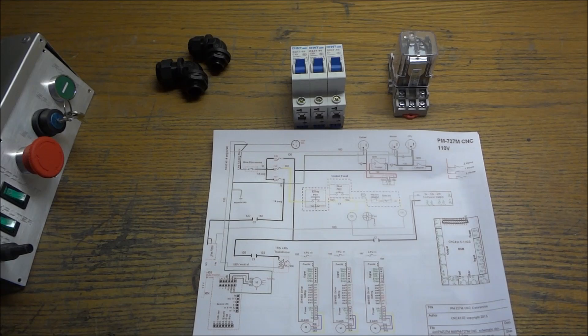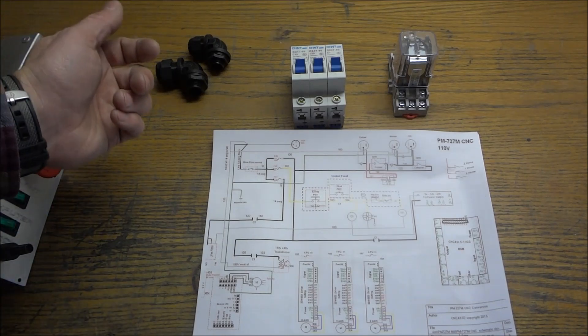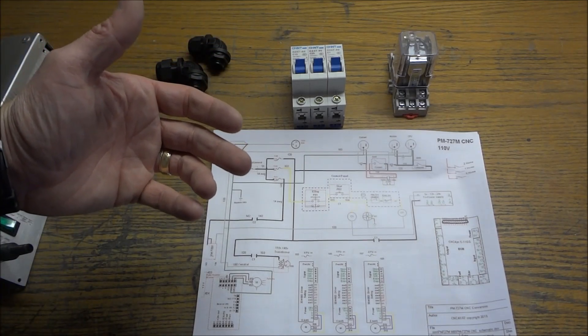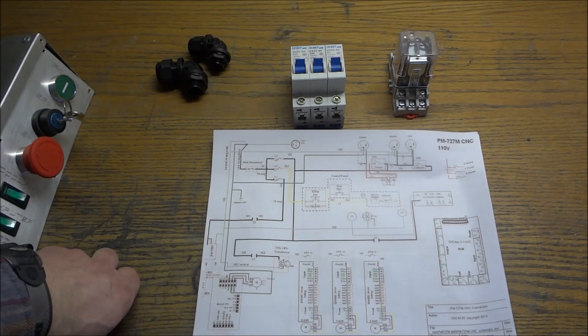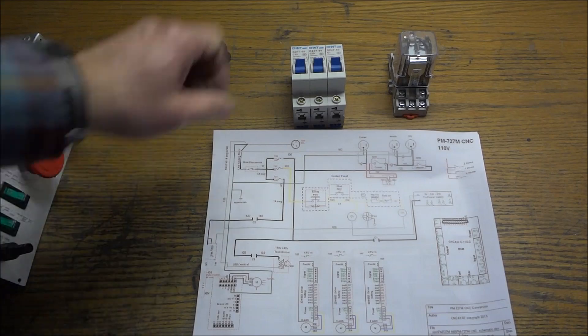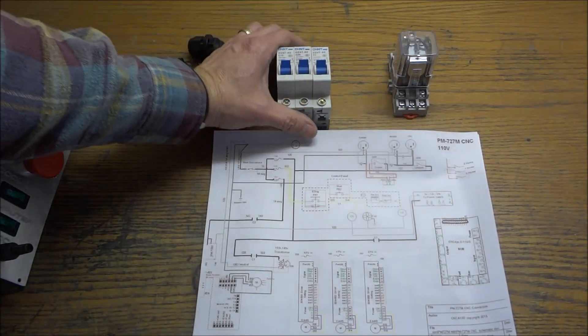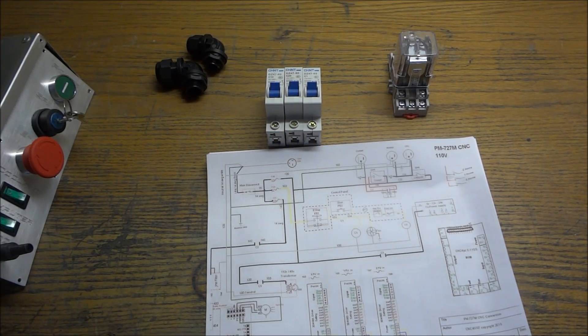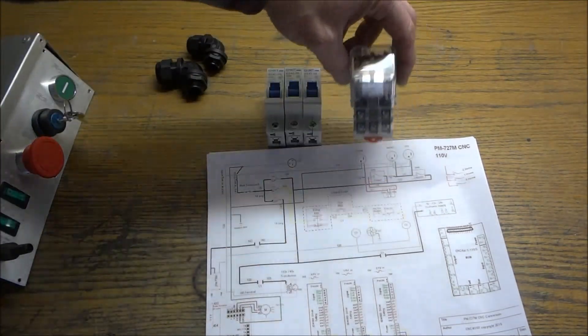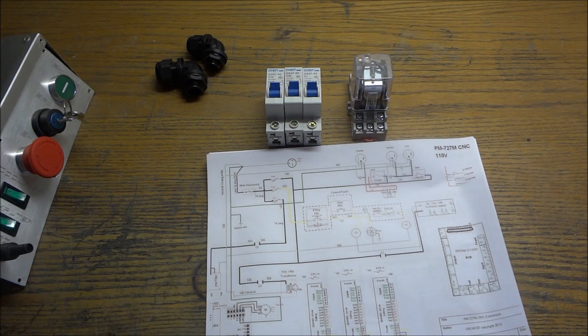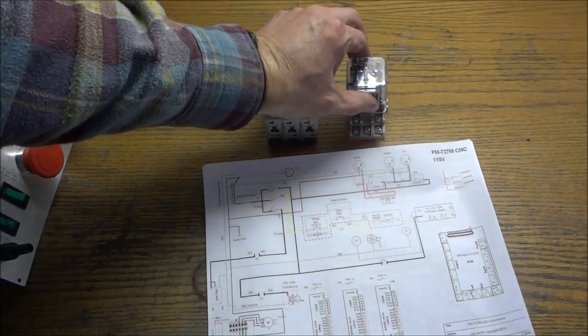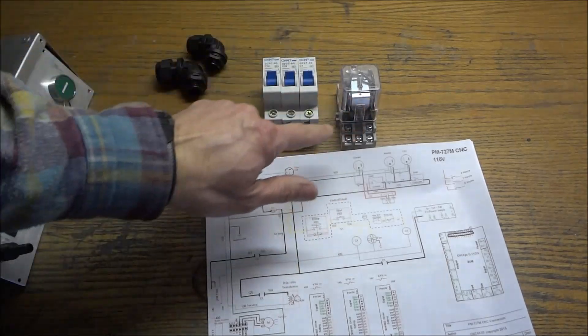With circuit boards, if you reset the breaker and you blow the board, then it's a lot more expensive than popping a fuse. So I would caution you with using the breakers. Now I did order some breakers and so I'll probably go ahead and install these in my cabinet and that'll just give you a different option. I've got to install my C1 contactor anyway, so I'll go ahead and do that. So now let's pull the enclosure out and then we'll replace the circuit breakers and also the C1 contactor and then I'll show you the difference with the wire numbers on the C1 contactor.